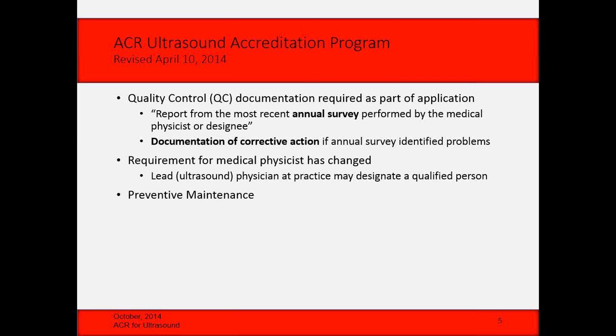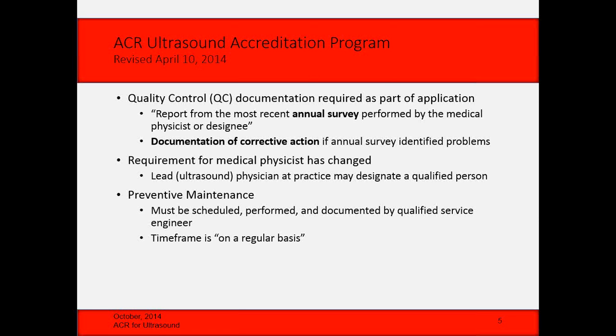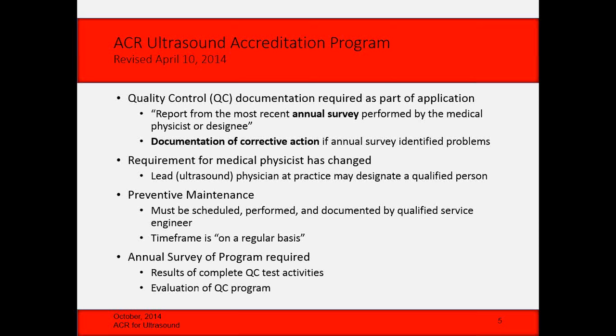Preventative maintenance as part of the ultrasound accreditation program must be scheduled, performed, and documented by a qualified service engineer. I'm going to explain what that means to ACR. The time frame they say you should do it on is on a regular basis. The time frame can be established sometimes by looking at the manufacturer's manuals, or you may want to make a determination yourself on the preventative maintenance schedule based on the risk that that system is under. So the higher the risk, obviously, the more often you would want to check that system to make sure things are correct.